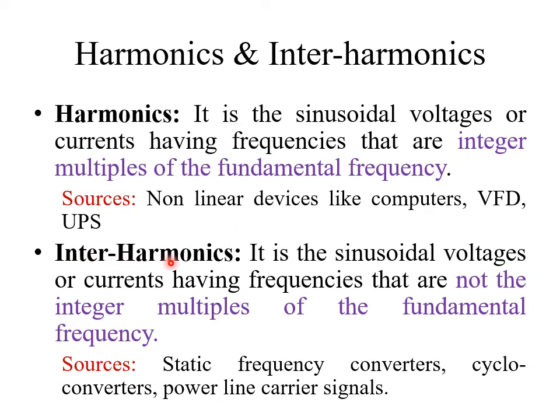Interharmonics are the vice versa of harmonics — those not captured under harmonics are called interharmonics. They are defined as currents or voltages whose frequencies are not integral multiples of the fundamental frequency. Sources of interharmonics include static frequency converters, cycloconverters, and power line carrier signals.